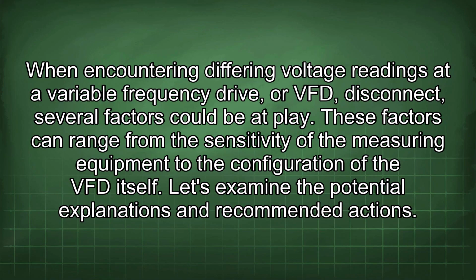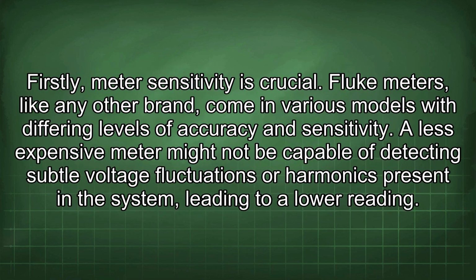When encountering differing voltage readings at a variable frequency drive, or VFD, disconnect, several factors could be at play. These factors can range from the sensitivity of the measuring equipment to the configuration of the VFD itself. Let's examine the potential explanations and recommended actions. Firstly, meter sensitivity is crucial.